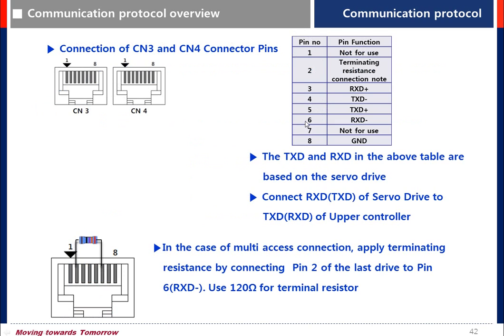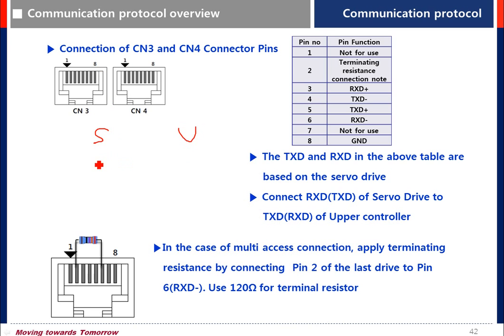This is the pin number and pin function. The pin function is based on the servo drive, so connect RXD of the servo drive to TXD of the host controller. Connect RXD+ to TXD+ in the same way. At the last drive, connect a terminal resistor of 120 ohm between pin number 2 and 6.